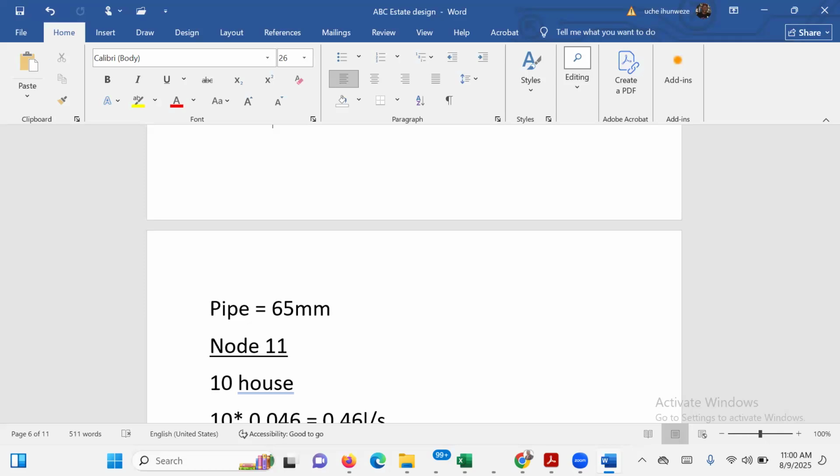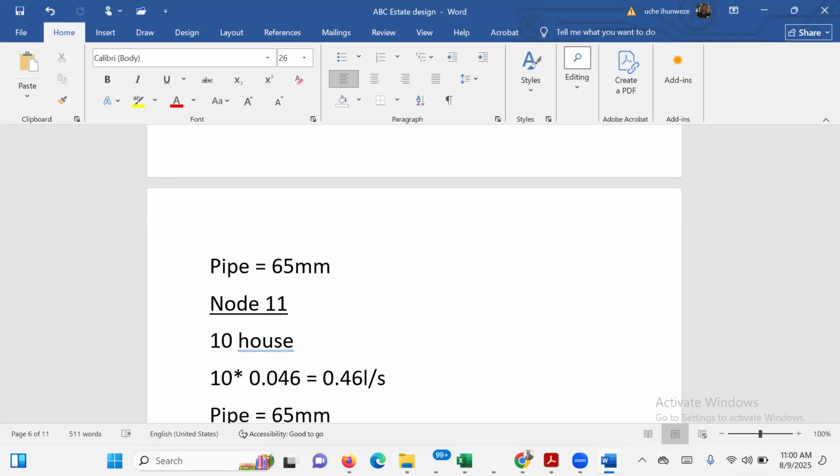So you can see that pipe sizing, the capacity of a pipe is not static, it's a range. That's why last week I also told us that your pipe should flow between 70 and 90% full for a pressured pipe, or you call it a closed pipe. It must not flow 100%. It must give a buffer, or would I say overboard? Is it overboard? That's the word again, freeboard. Okay. So go to node 10.